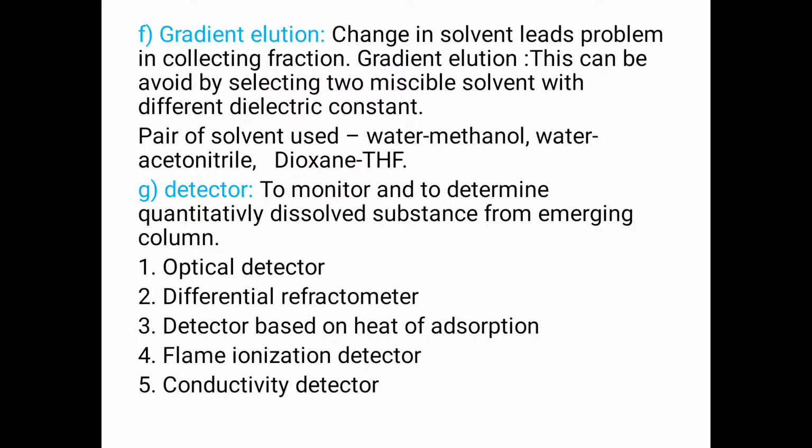Then differential refractometers. In the differential refractometer, the refraction of the emerging eluent is employed for detection, and this method has been improved to a differential refractometer having a detection sensitivity limit of 10 raised to minus 6 gram.